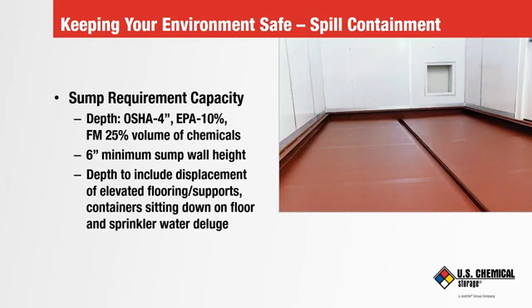Common sense and being practical is also required. If the containers are sitting down on the sump floor, then the amount of sump capacity or its wall height must be increased by the displacement factor of the total number of the stored containers. If the containers are placed on an elevated floor, then any of the support structure involved in the elevated floor's construction is also to be considered for its displacement factor.